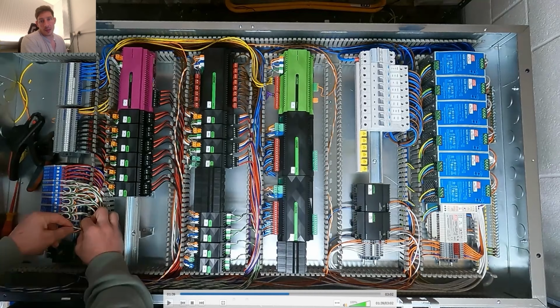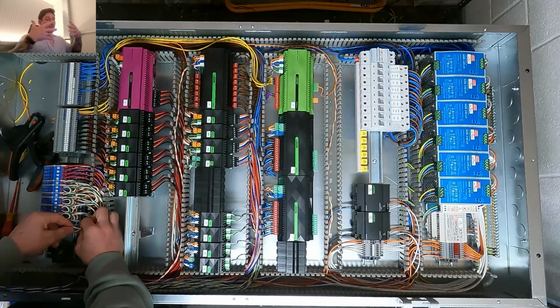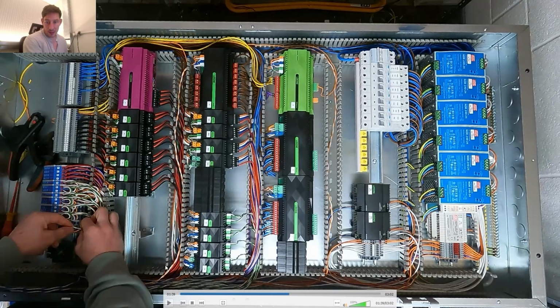So here what I'm doing is adding, because now these grey terminal blocks are similar to the blue ones, but rather than being galvanically isolated, like this section is isolated from that section, the grey terminal blocks are all common together. If you put say 24 volts in, it's spread across all of those terminals.